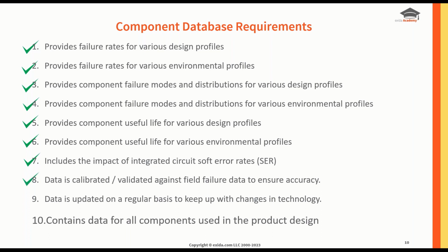The data also needs to be calibrated and validated against field failure data to ensure accuracy. What I mean by this is that it's okay having a database, but it can't be stagnant. You can't have just your failure rates, and in 5 years' time the same failure rates are sitting there. You need to be comparing to real-world field failure data, looking at the metrics from there, and then feeding that back into your database to see, do you need to update your components within the database.